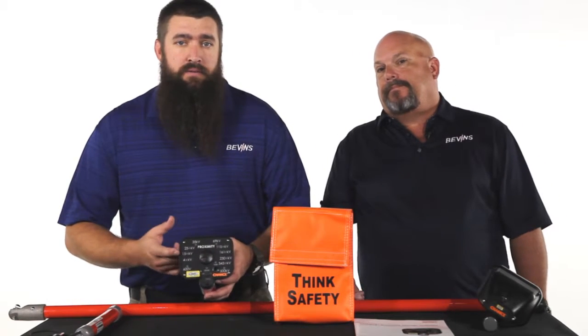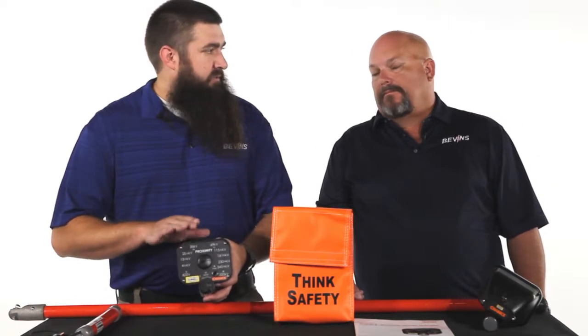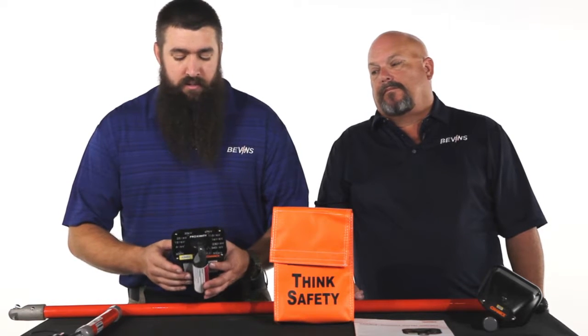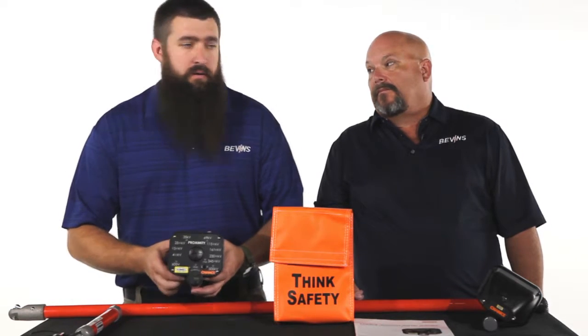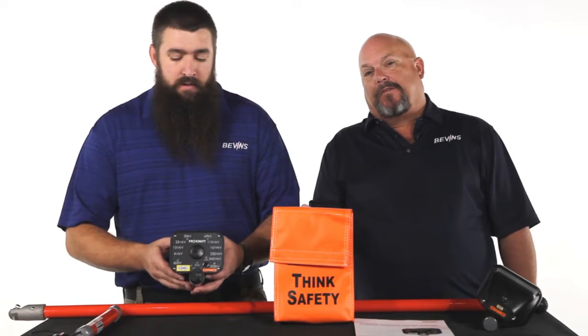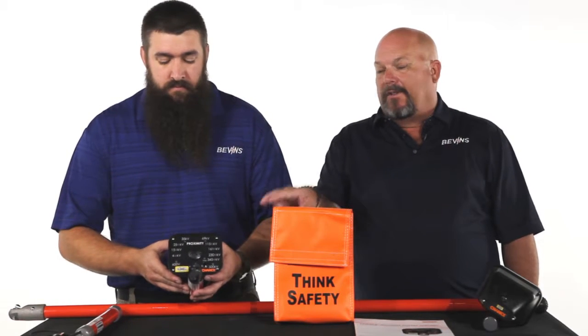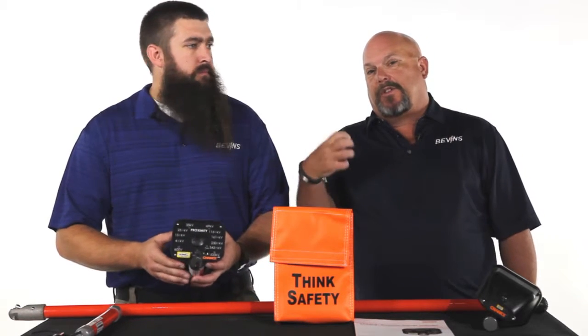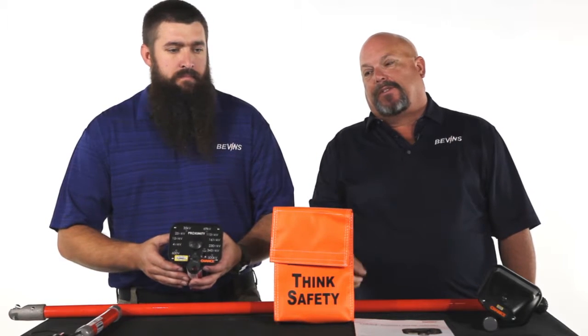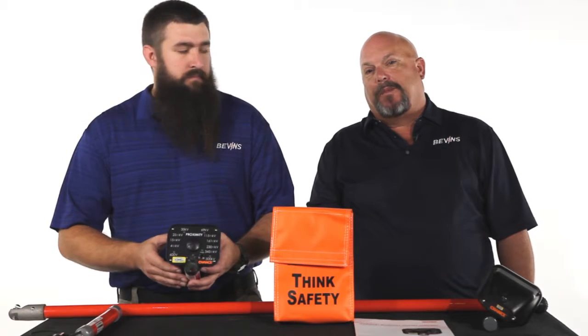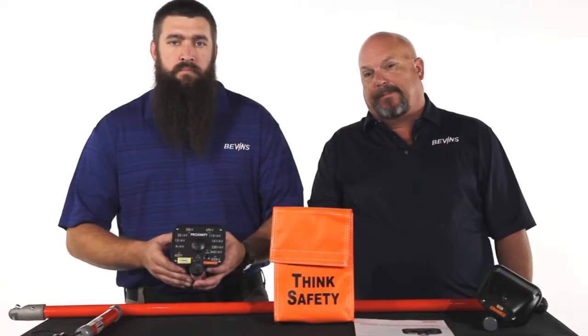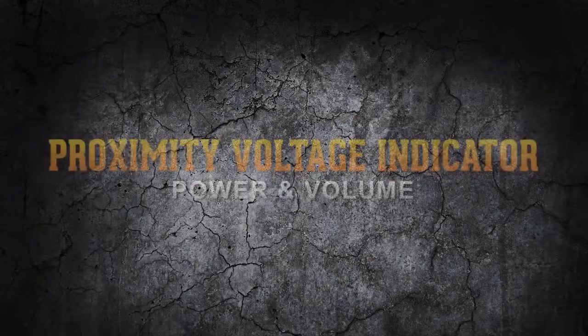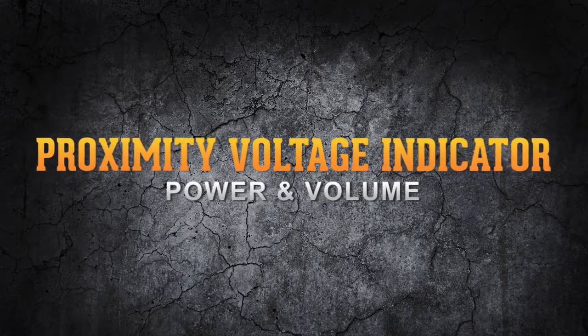So it just allows the user a little bit more explanation of just what those ranges or those classes are telling them. Very good. And of course, we're reading phase to phase. Now, if you see two lights on at once, that means you're just in between the classes of voltages. Again, refer to the instruction manual for what everything means. Proximity was designed from capacitive test point to 500 kV, phase to phase.